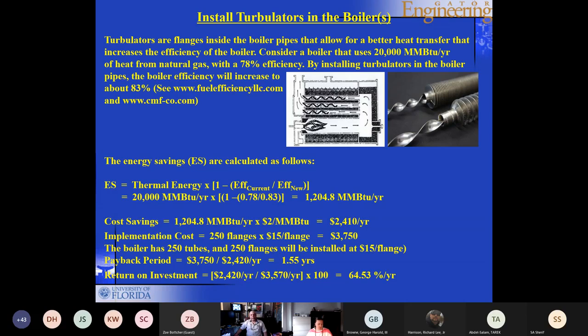The energy savings will be calculated as the thermal energy that you need, 20,000 million BTUs per year, which you're going to put into that boiler, multiplied by 1 minus the current efficiency divided by the new efficiency. So 78% divided by 83%, you save 1,204 million BTUs per year. Now this is natural gas. The natural gas costs $2 per million BTUs, so you're looking at $2,410 per year.